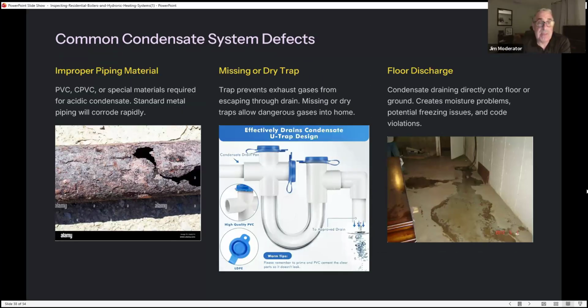Common condensate system defects: improper piping material. PVC, CPVC, or specialized material is required for acid condensate. Standard metal piping will corrode rapidly. Missing or dry trap: traps prevent exhaust gases from escaping through the drain. Missing or dry traps allow dangerous gases into the home. Floor discharge: condensate draining directly onto the floor or ground creates moisture problems, potential freeze issues, and code violations.